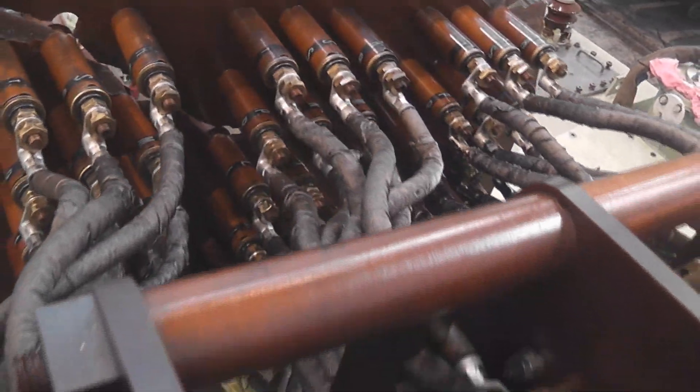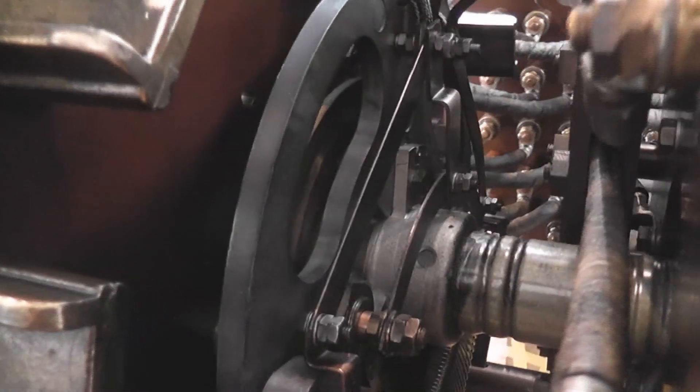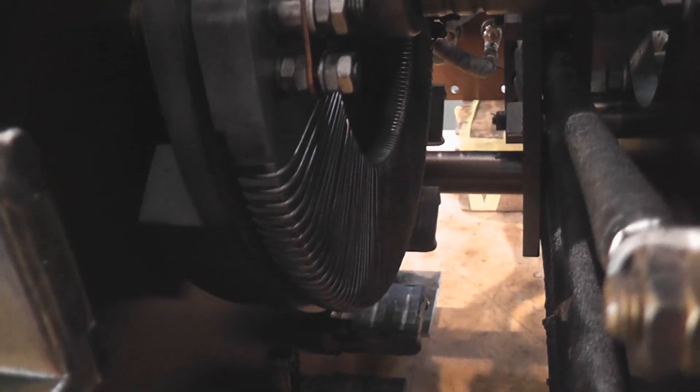Three phases, and here we go into the other module. Those are the actual contacts. Big power resistors in here during the tapping, because you are not allowed to have two taps in parallel. Big resistors while switching around.